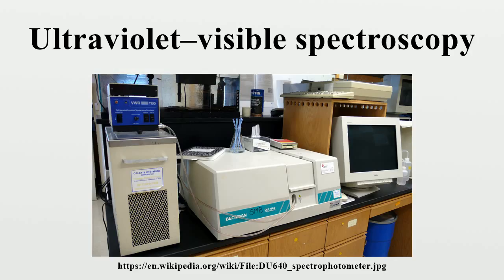The radiation source is often a tungsten filament, a deuterium arc lamp which is continuous over the ultraviolet region, a xenon arc lamp which is continuous from 160 to 2,000 nanometers, or more recently light-emitting diodes for the visible wavelengths. The detector is typically a photomultiplier tube, a photodiode, a photodiode array, or a charge-coupled device. Single photodiode detectors and photomultiplier tubes are used with scanning monochromators, which filter the light so that only light of a single wavelength reaches the detector at one time. The scanning monochromator moves the diffraction grating to step through each wavelength so that its intensity may be measured as a function of wavelength. Fixed monochromators are used with CCDs and photodiode arrays.